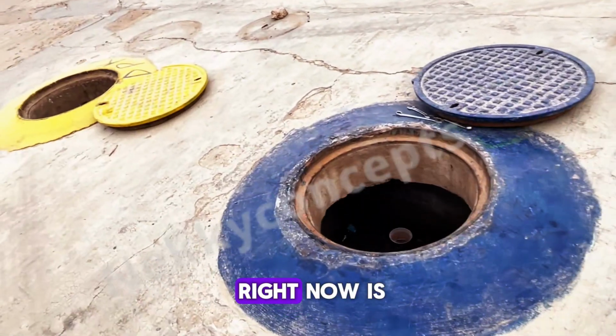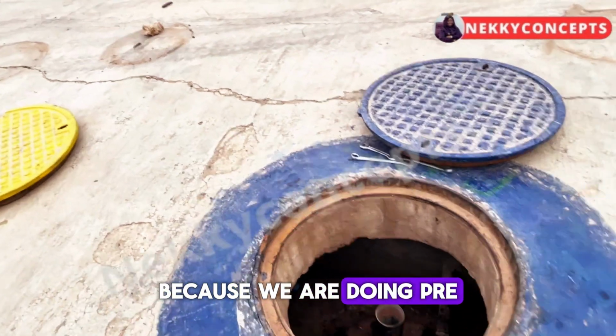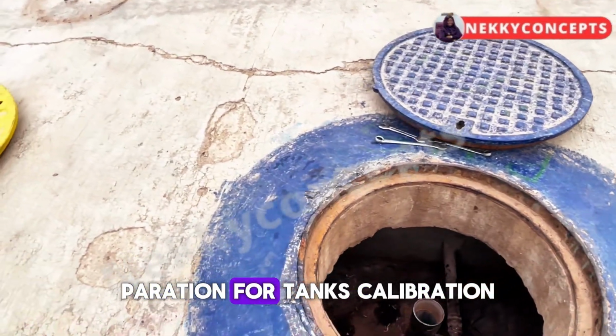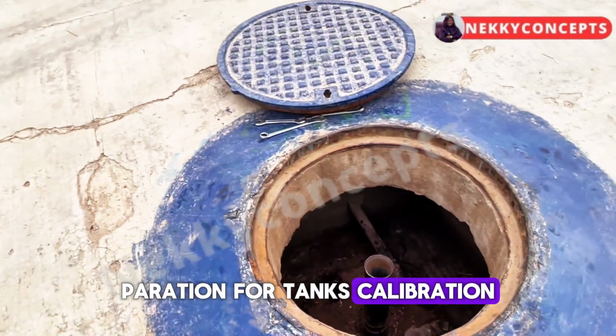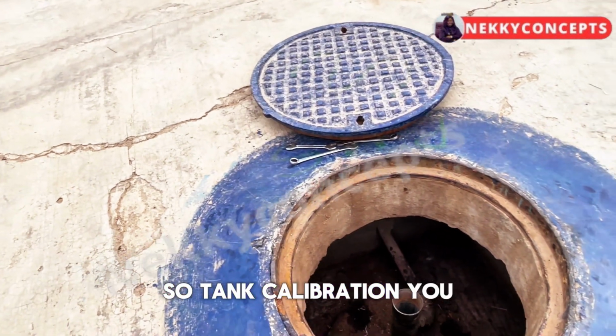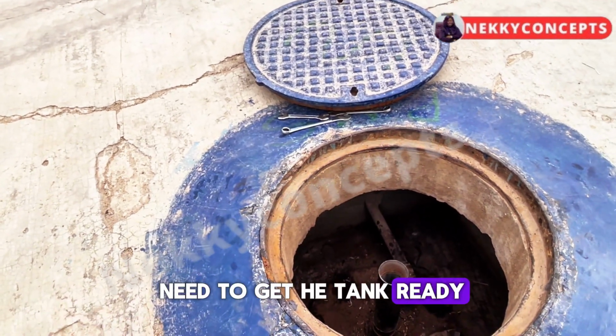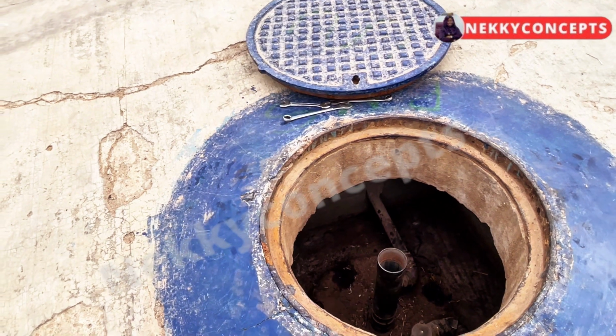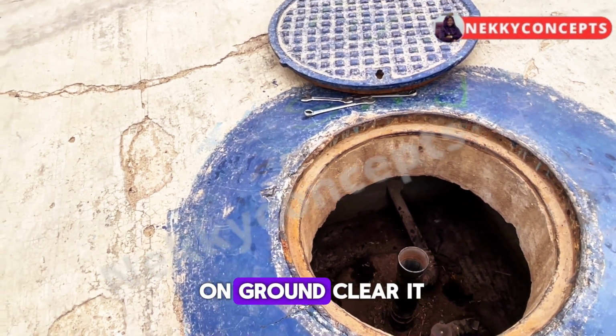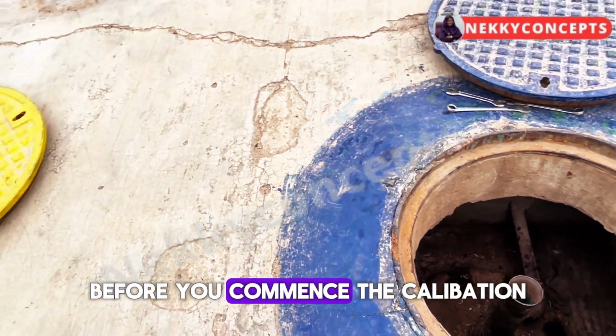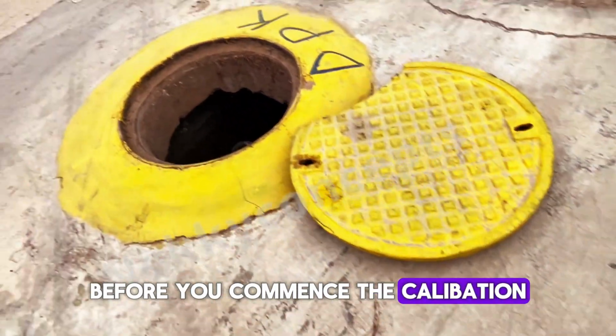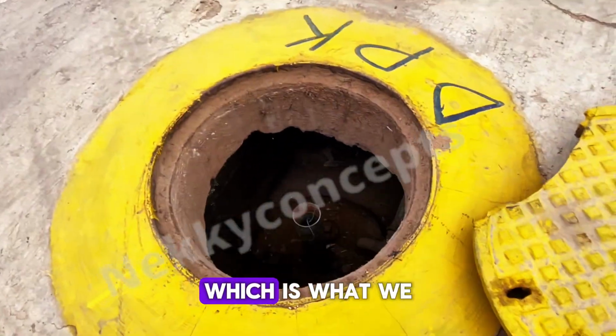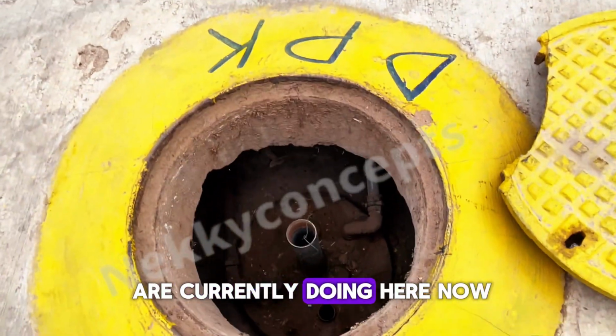So what is happening here right now is we are doing preparation for tank calibration. For tank calibration, you need to get the tanks ready, open the manholes, remove the product that is on ground, clear it, and clean it before you commence the calibration, which is what we are currently doing here now.